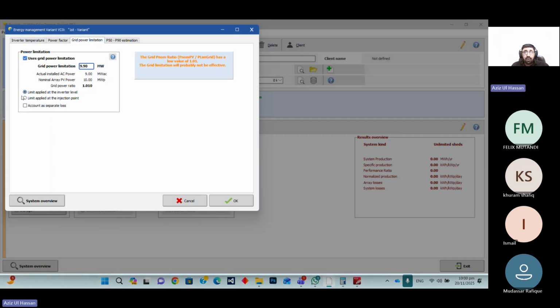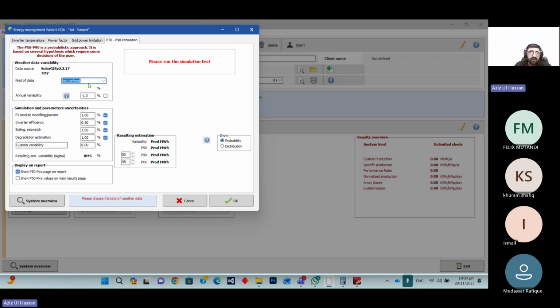Okay, so now there are different options: limit applied at the inverter level, limit applied at the injection point, and account as a separate loss. Now, as per their contract, in most cases it should be applied at the injection point. Most cases account as a separate loss, but you have to do that option for large scale projects, 100 megawatt, 200 megawatt. You have to apply the grid limitations. Okay, so this option is available there.